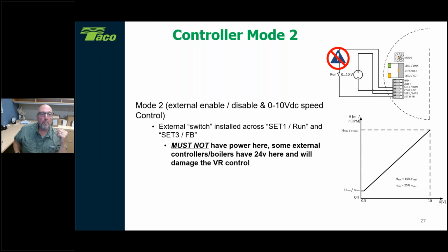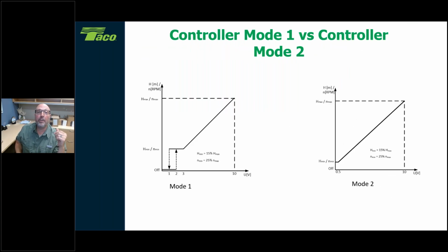Steve's follow-up is, what is the difference between mode 1 and mode 2? All right, here's your mode 1 versus mode 2. It's going to be that 0 to 10 signal coming in. So mode 1 says there's a minimum speed once you get to a 3 volt signal. So there are some boilers and some equipment out there that don't like to have zero flow if they're still flowing, going through the heat exchanger.